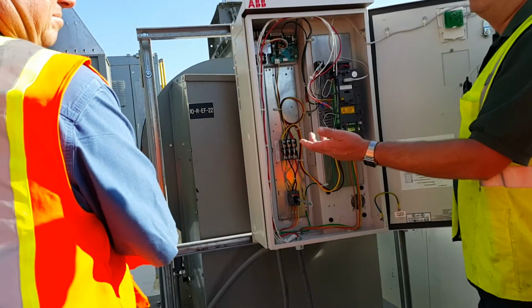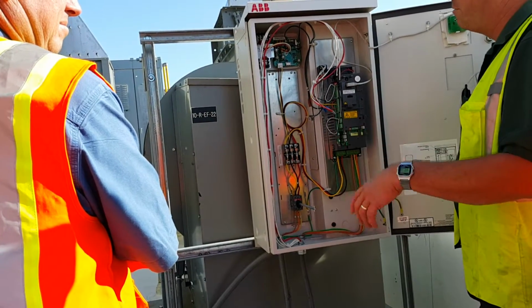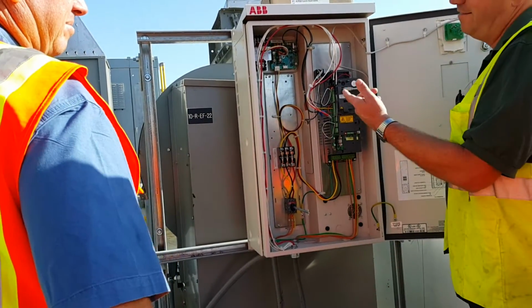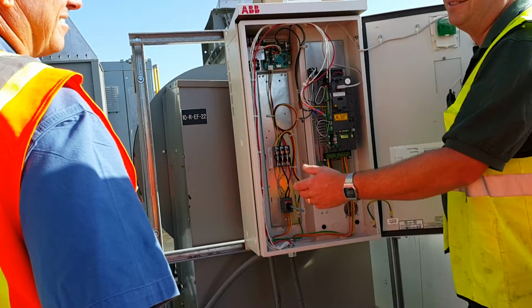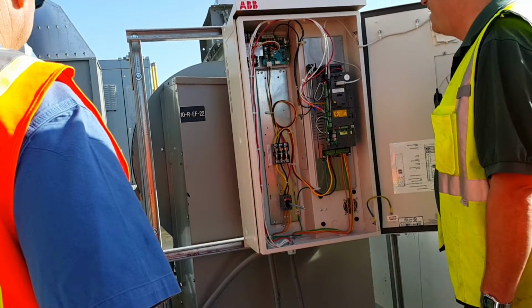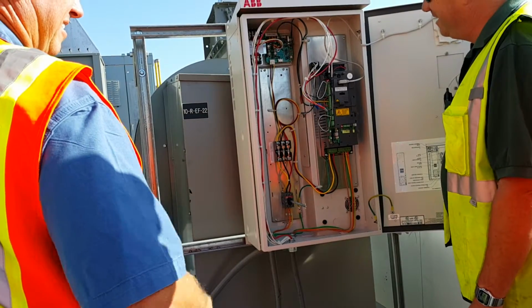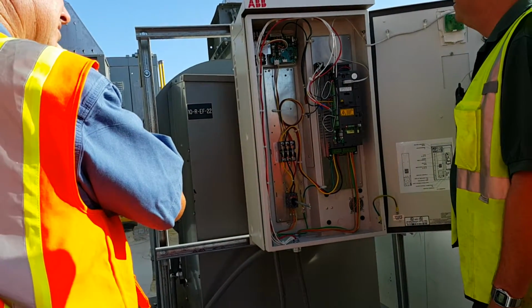And sometimes you get that call too. So the drive says it's doing 60 hertz. Something wrong with it. It's 0 amp. And I realize they have the disconnect open through the drive. Just a local disconnect, things like that. You gotta hook up that motor. It doesn't know otherwise. It's not magic. Got it.